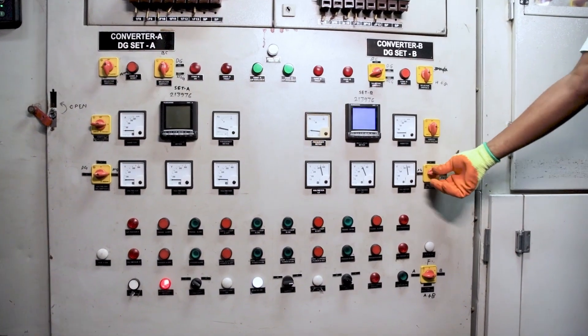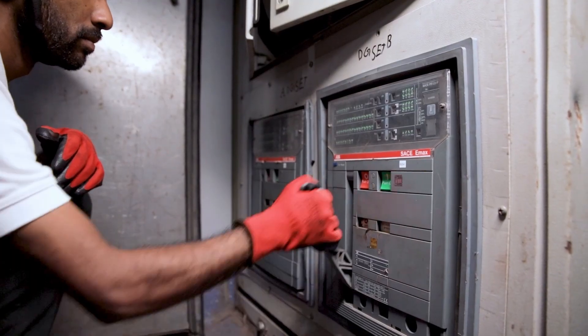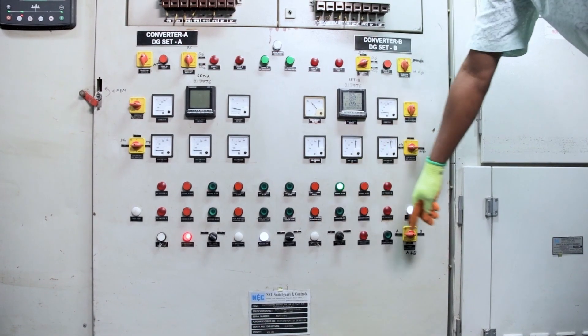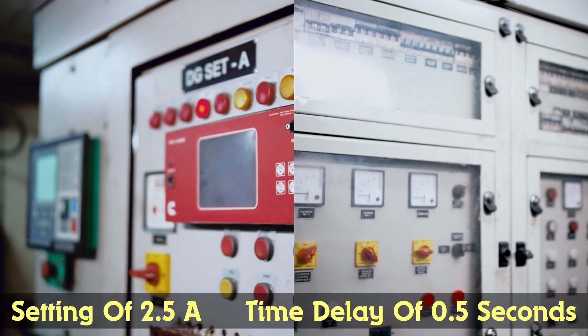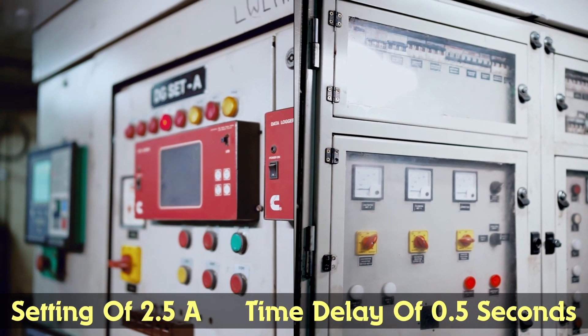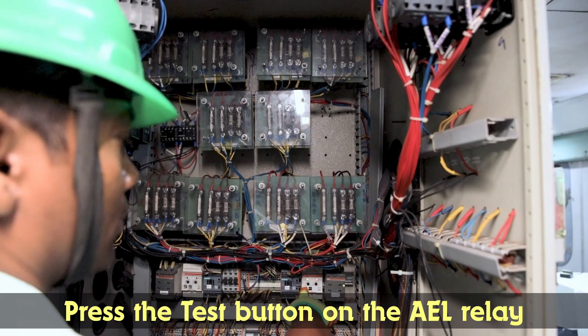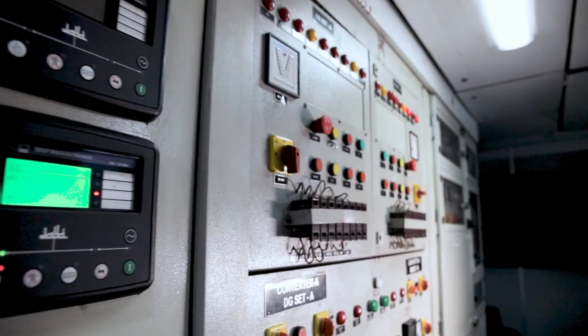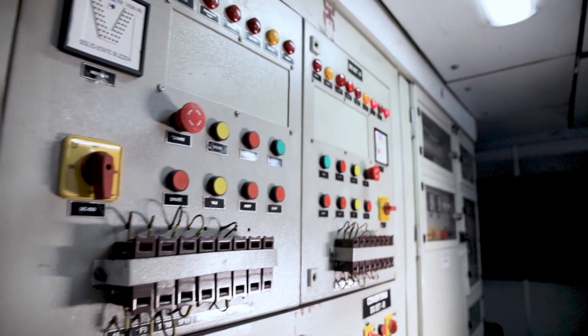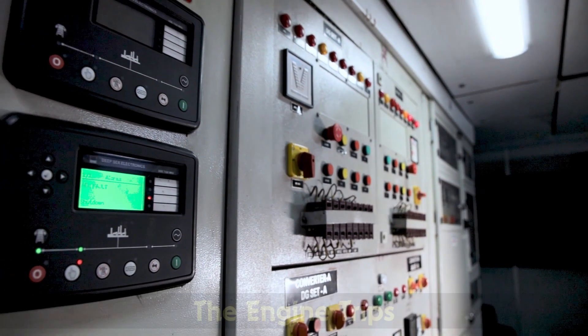We now check or set the Earth fault relay with a current setting of 2.5 amps and a time delay of 0.5 seconds. Press the test button on the AEL relay. After the red signal appears on the AEL relay, the AEL indication light turns on and the engine trips.